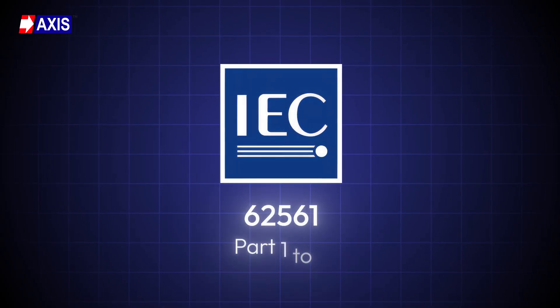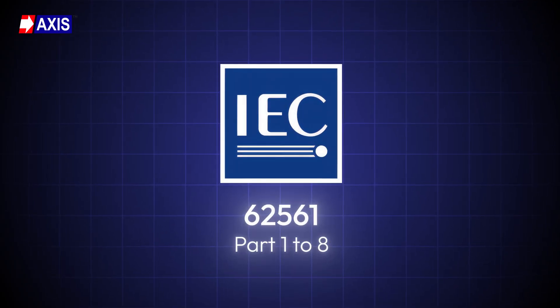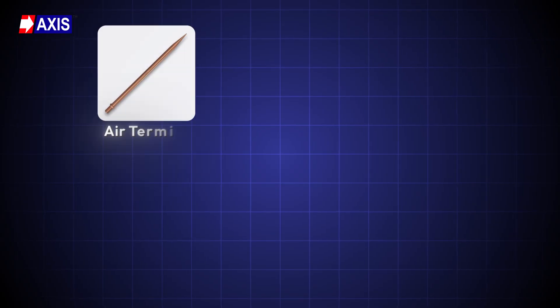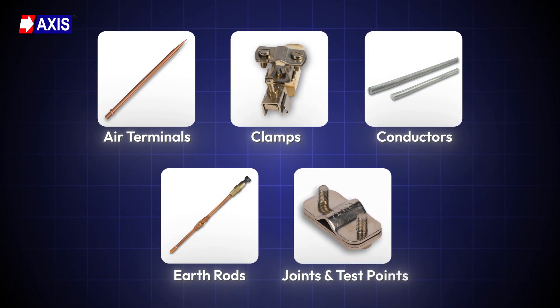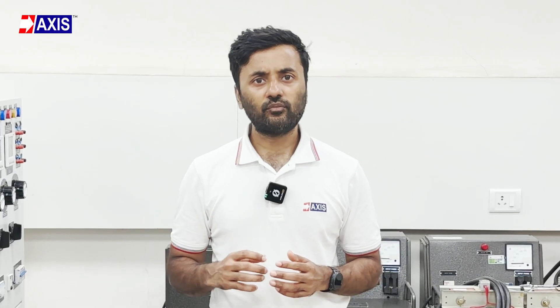Number 10, IEC 62561, Part 1 to Part 8. This standard defines the performance and testing requirements for all components used in an external lightning protection system. It covers air terminals, clamps, conductors, earth rods, joints, and test points. Use IEC 62561 when you are selecting or approving materials for a lightning protection system. It ensures that every component is tested for strength, corrosion resistance, and conductivity.